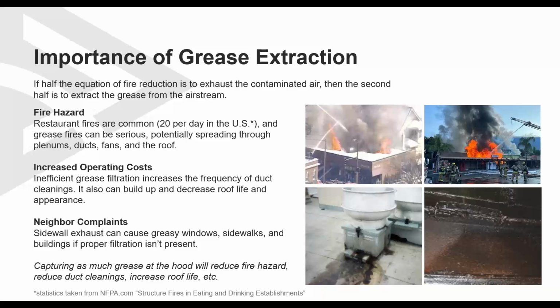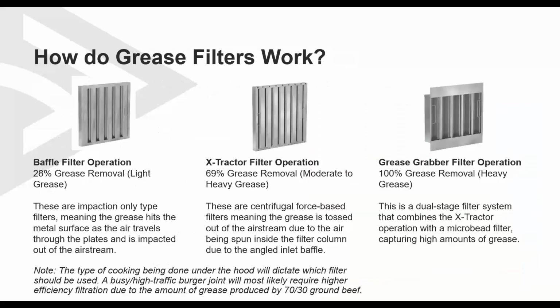Inefficient grease filtration increases the frequency of duct cleanings. It also can build up and decrease roof life and appearance. You may also have neighbor complaints. From sidewall exhaust fans, they can cause greasy windows, sidewalks, and buildings if proper filtration isn't present. The idea is capturing as much grease at the hood will reduce fire hazard, reduce the duct cleanings, and increase roof life, etc.